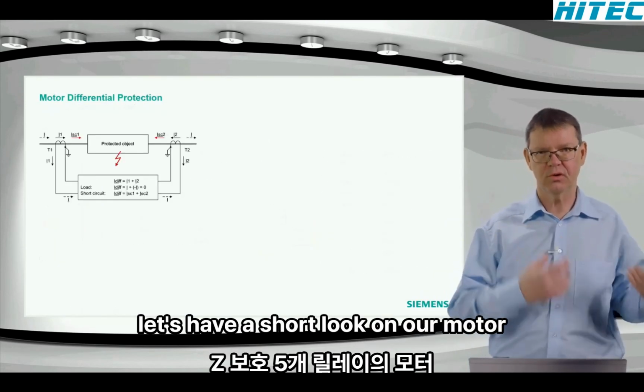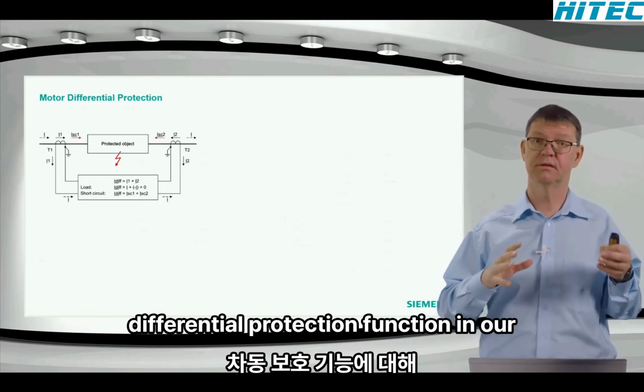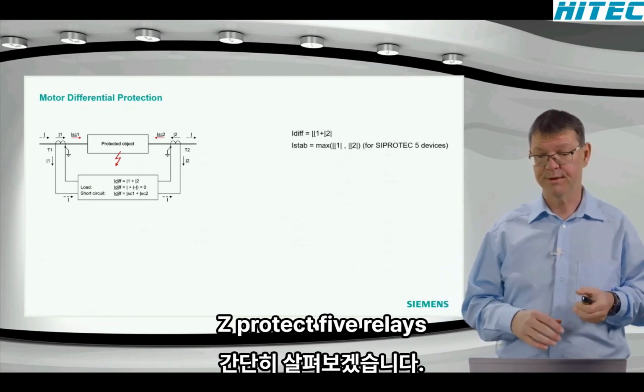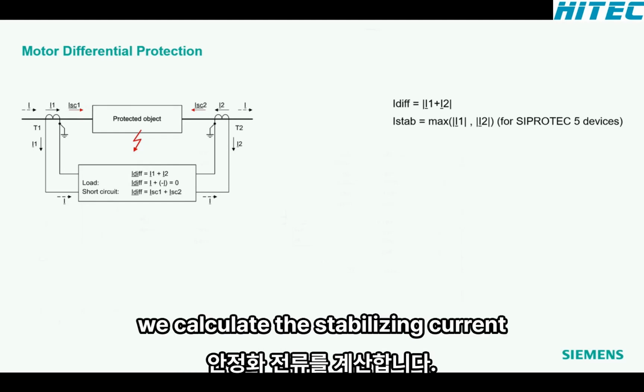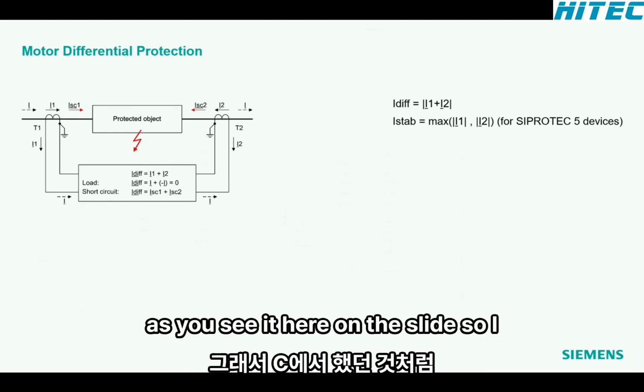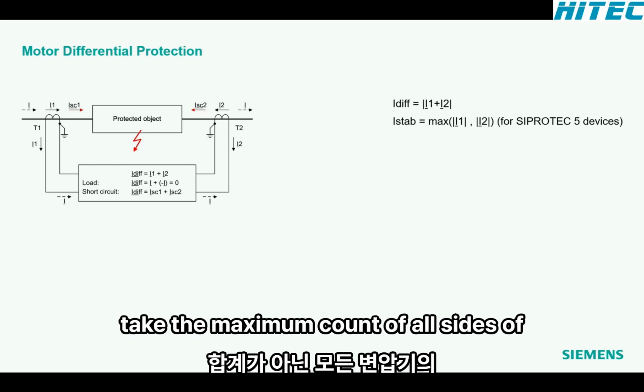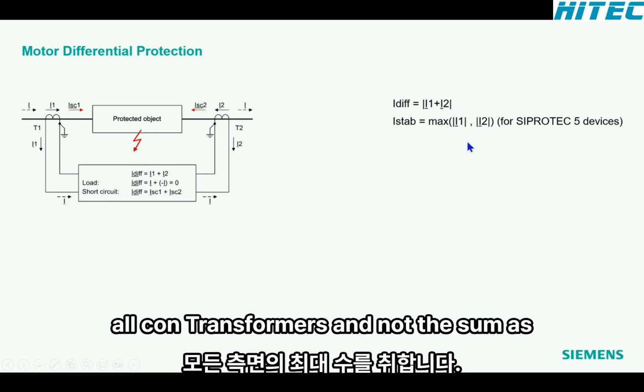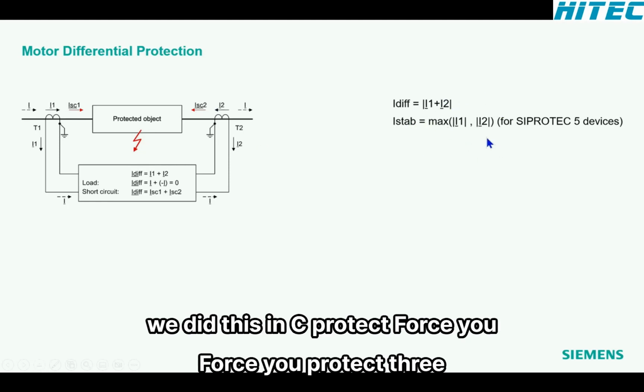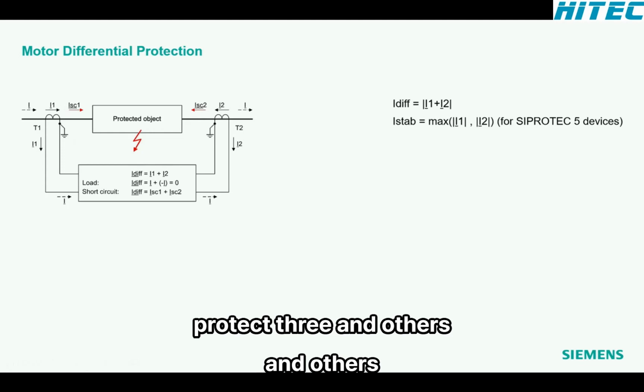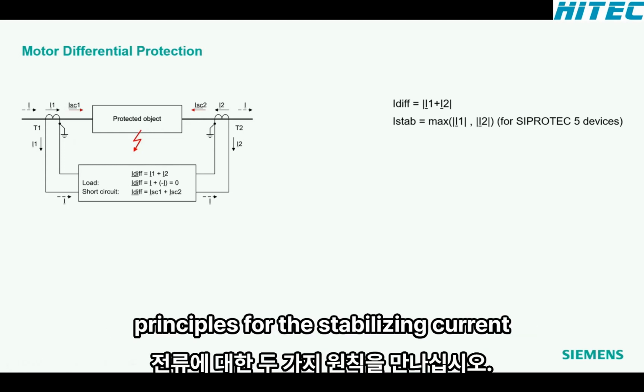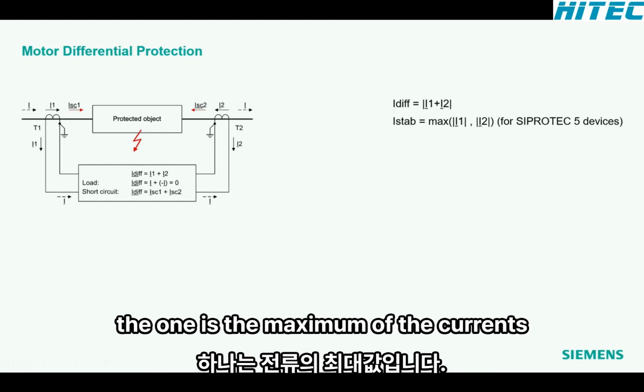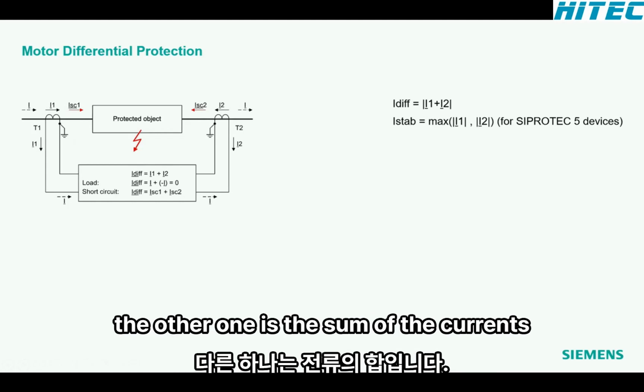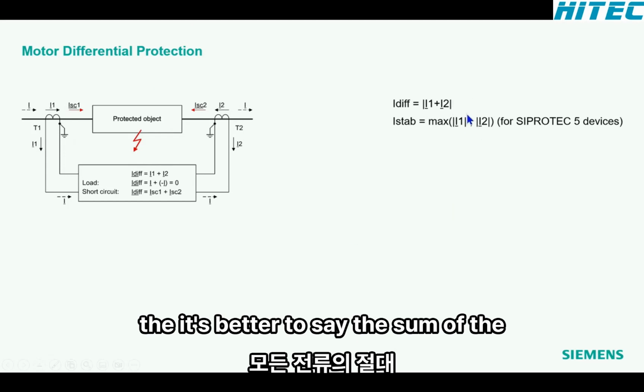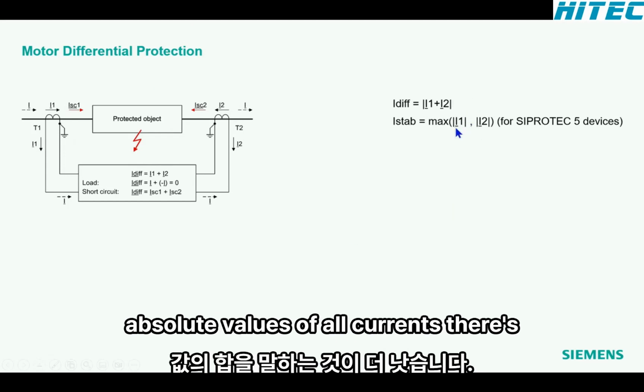Good. Let's have a short look at our motor differential protection function in our SIPROTEC 5 relays. First of all, we calculate the stabilizing current as you see it here on the slide. So I take the maximum current of all sides, of all current transformers, and not the sum as we did this in SIPROTEC 4, SIPROTEC 3 and others. And here we encounter basically the two principles for the stabilizing current. The one is the maximum of the currents, the other one is the sum of the currents. It's better to say the sum of the absolute values of all currents.